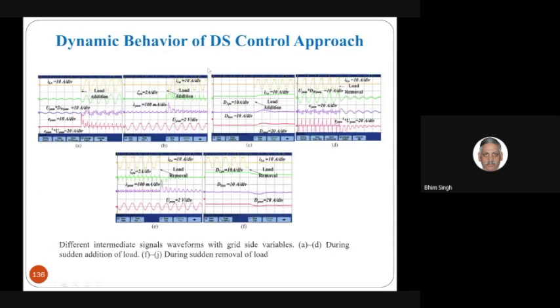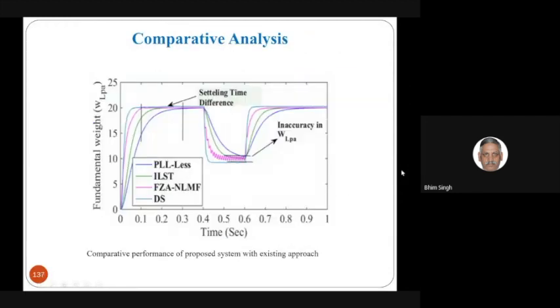Here you can clearly see what happens when the load is switched on: how the grid currents and inverter currents work as an active filter, and how different control signals start working when the load is added or removed. How the signals really change in this system, and how the performance compares among all four techniques.